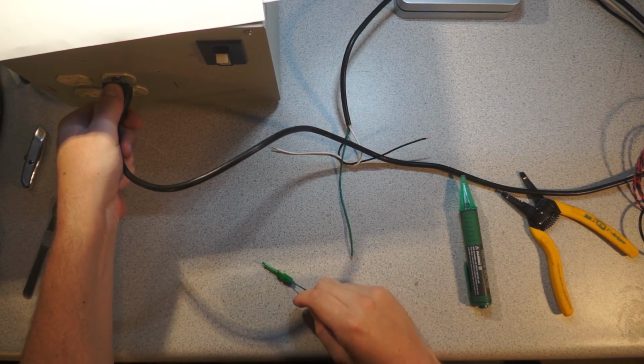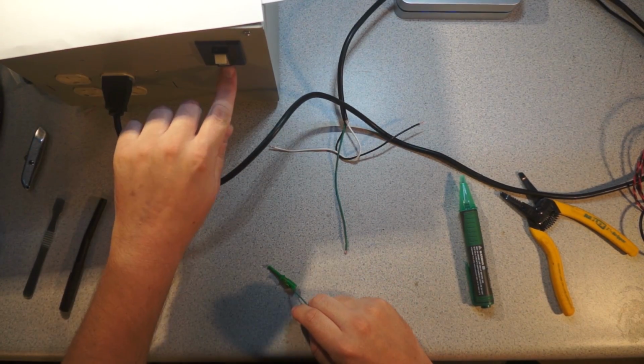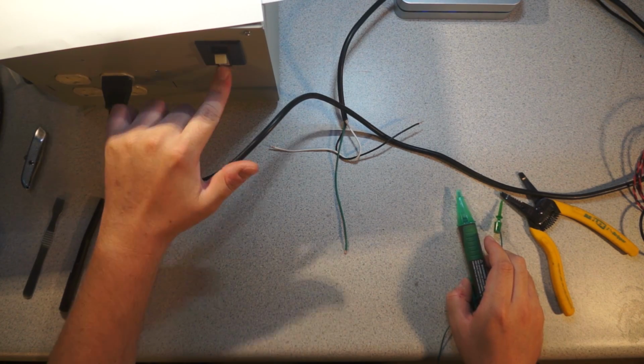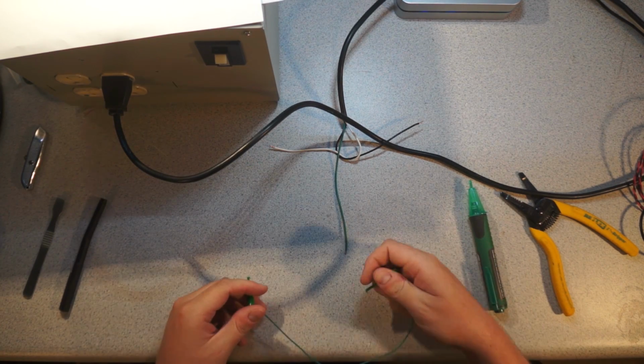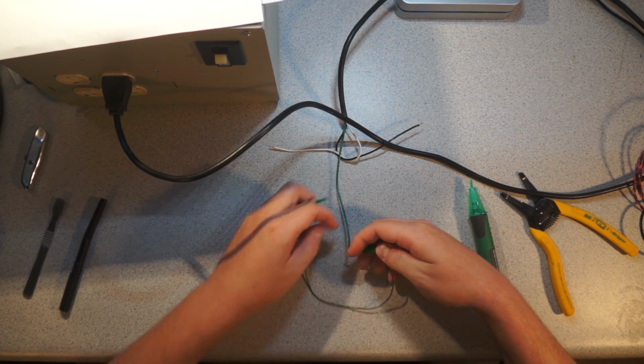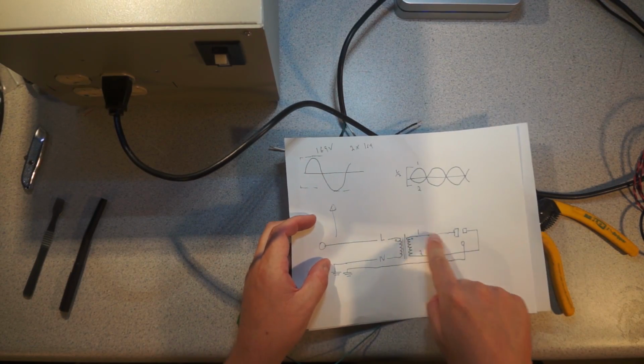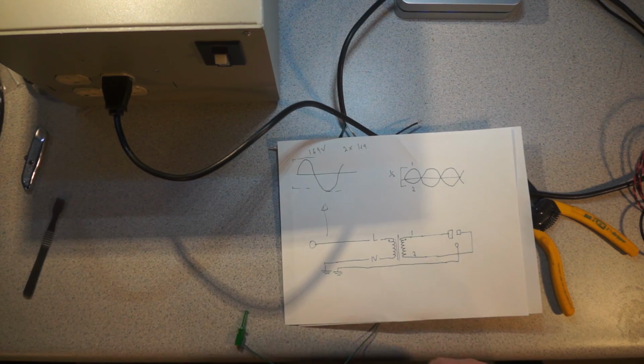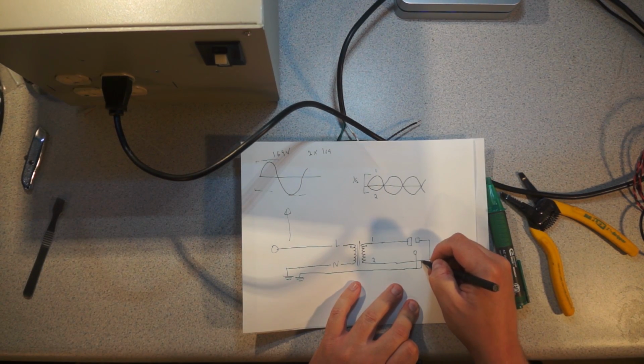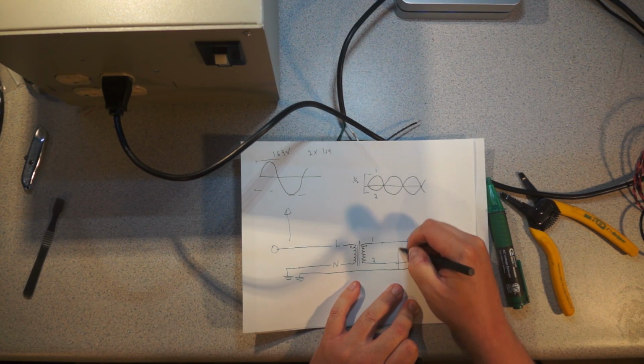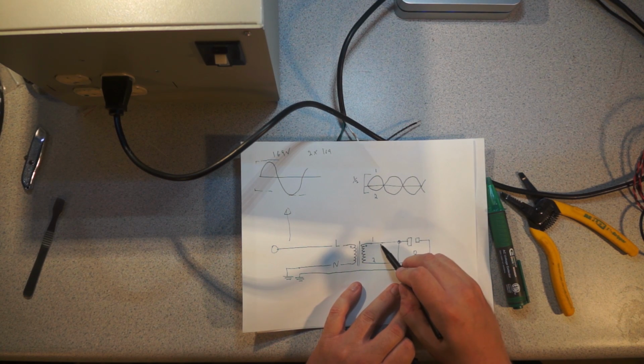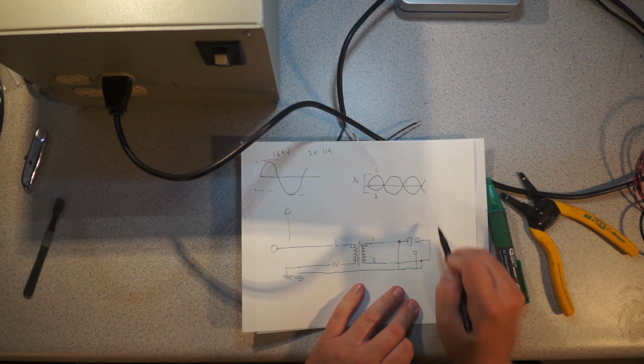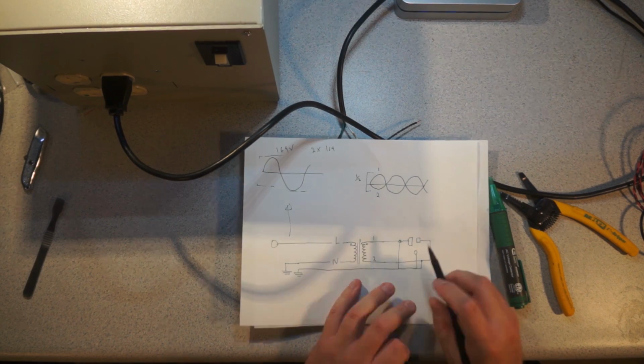So if we go in here, this transformer is currently off, and you can see the on and off. What we should be able to do safely is ground either one. Remember, because these are both floating with reference to the ground, we can optionally tie the ground to either this winding or this winding. So we can say we want this winding to be our earth referenced, and then this winding will swing up and down relative to that one, or vice versa.